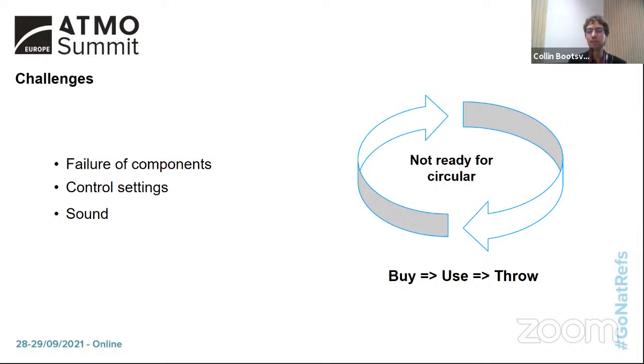I don't want to give a detailed analysis, just to mention that we have compressors, heat exchangers, expansion valves, joints. Everything can break, and it does. That's a real problem, because we then go to the manufacturer of the heat pump or chiller and say it's broken, it's your responsibility. But that manufacturer usually can't do much because he's dependent on a supplier of the components.